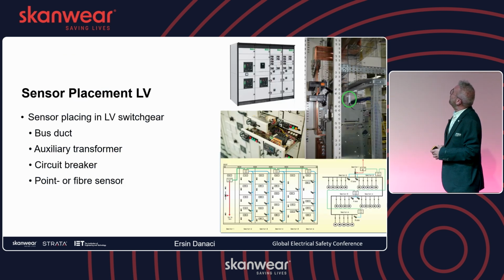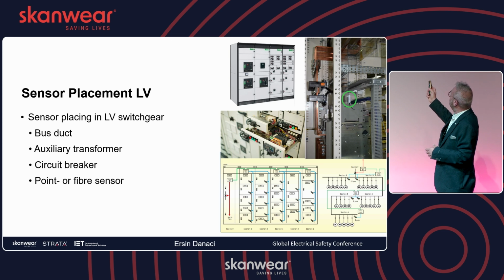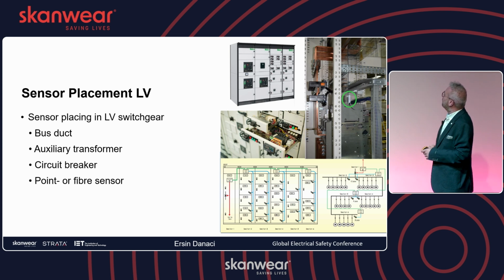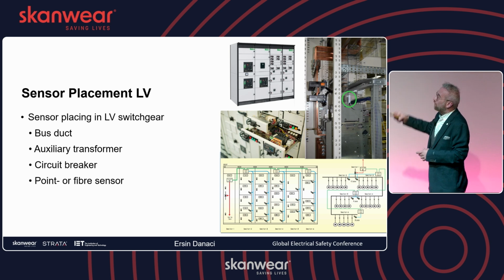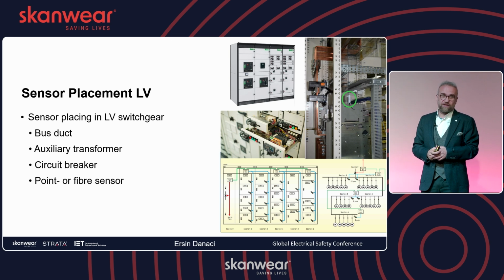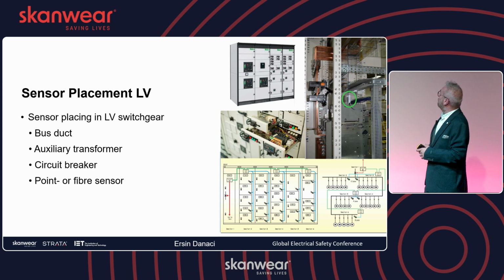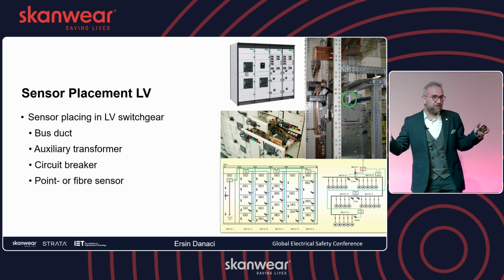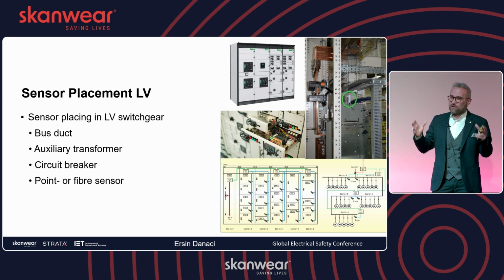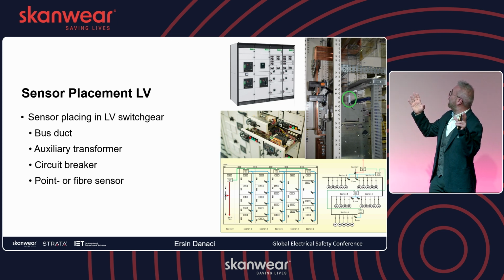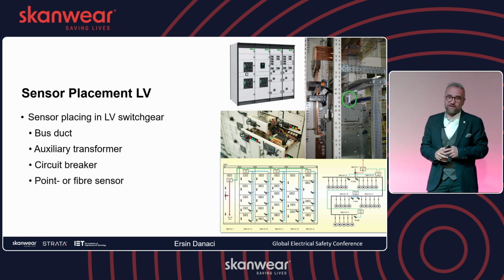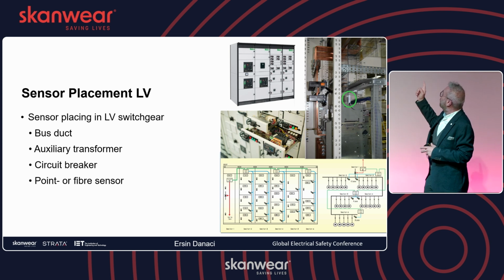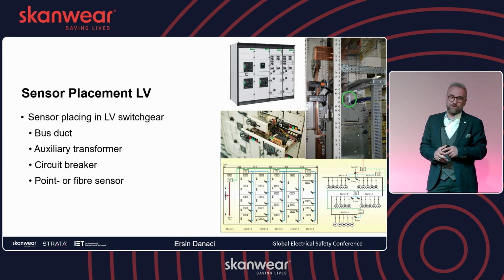So here we have some examples for the LV switchgear. As you can see, there's a single line diagram here. Blue color is the loop for the fiber optic circuit, and the green line is the communication between extension tools. Usually, if it's more than 20 or 30 switchgears, we propose to use a central unit on the main board, and also extension modules for the other LV circuits, just to utilize more optical sensors.